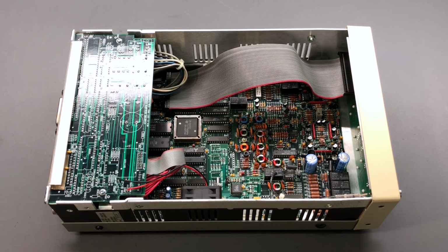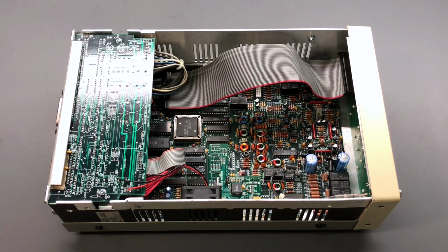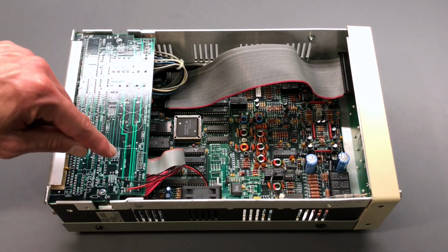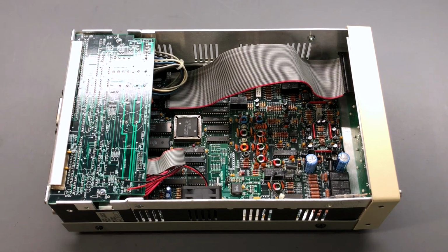Now again, the factory set of cal bytes stored in ROM should be good for most of the adjustments, because the rest of the circuitry in here really doesn't drift over time. I mean, it's very, very stable. But the crystal oscillator certainly can drift over time and needs some correction. So as it is now, if we go in and make a change on the data that's in RAM, if this battery is dead, it will be lost, and the next time you power up the instrument, you'd have to start all over again with a new calibration.